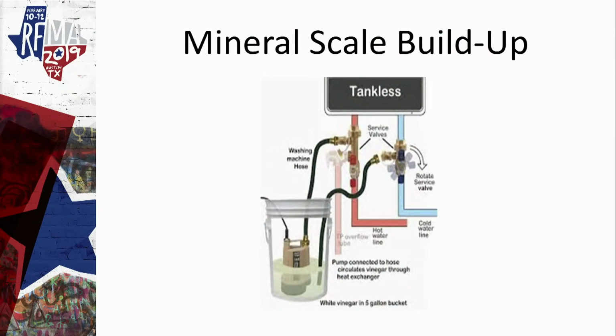If you use tankless, do a de-liming bath every year. What happens with the tankless piece of equipment is the heat exchanger -- what we call a boiler heart attack -- hard water will start to accumulate on the inside of the heat exchanger, and it slowly closes those tubes down. Kind of like my body now at my age, my arteries are getting smaller and smaller because of the way I ate. But if you do a de-liming kit and clean it out annually, you'll prolong the life of that equipment for a good period of time.